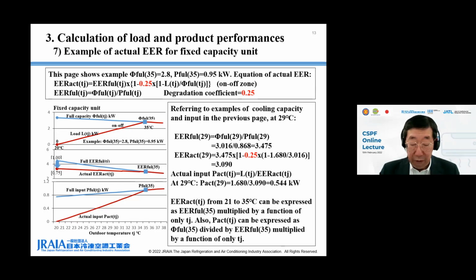The upper and middle figures in this page are the same as the figures for the fixed capacity unit in the previous page. And the lower figure shows full and actual input at each Tj, referring to the example of cooling capacity and input in the previous page. 29 degrees C full EER is full capacity 3.016 kilowatt divided by full input 0.868 kilowatt, equal to 3.475. From the equation in this page, 29 degrees C actual EER becomes 3.090.